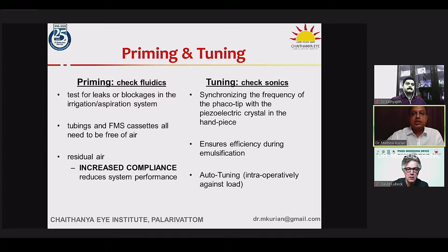The tuning of the machine is to check the sonics, and basically at this stage, the machine is synchronizing the frequency of the phaco tip with the piezoelectric crystals in the handpiece. Preoperatively, it is done in BSS, where there is no load, and most machines today have a facility to auto-tune, which is intraoperatively against the load of the nucleus. It is actually rechecking and ensuring that it is delivering the power that you have set.